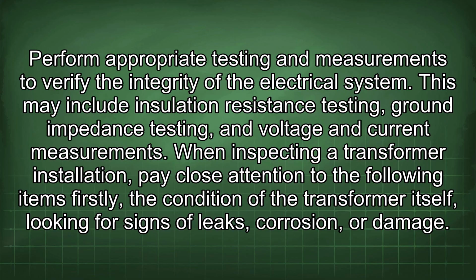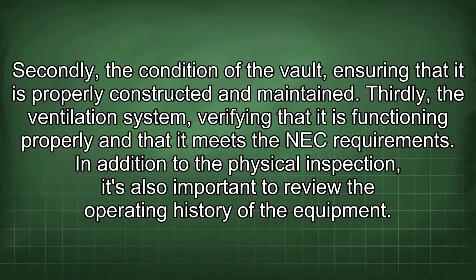When inspecting a transformer installation, pay close attention to the following items. Firstly, the condition of the transformer itself, looking for signs of leaks, corrosion, or damage. Secondly, the condition of the vault, ensuring that it is properly constructed and maintained. Thirdly, the ventilation system, verifying that it is functioning properly and that it meets the NEC requirements.